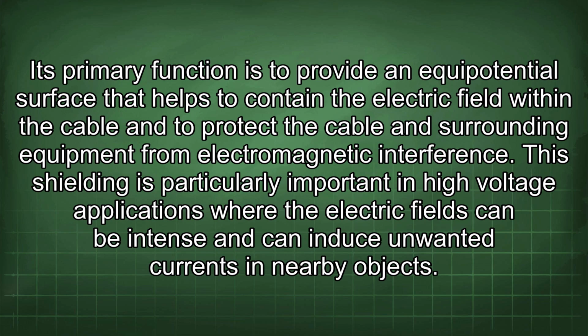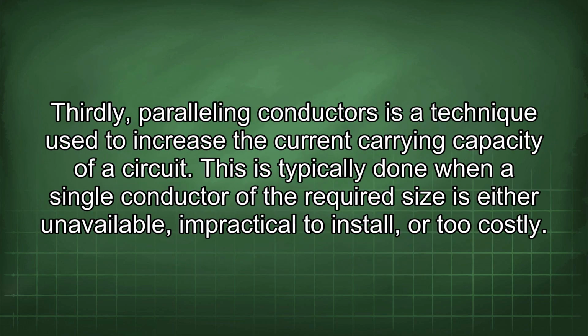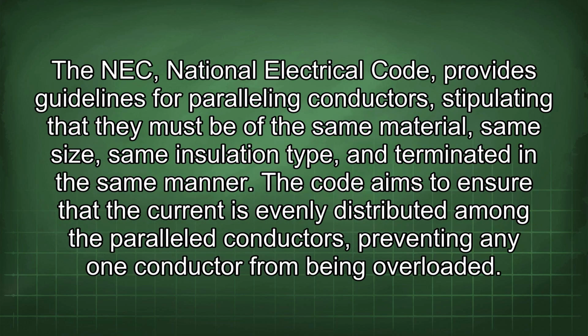The shielding is particularly important in high-voltage applications where the electric fields can be intense and can induce unwanted currents in nearby objects. Thirdly, paralleling conductors is a technique used to increase the current carrying capacity of a circuit. This is typically done when a single conductor of the required size is either unavailable, impractical to install, or too costly. The NEC, National Electrical Code, provides guidelines for paralleling conductors, stipulating that they must be of the same material, same size, same insulation type, and terminated in the same manner. The code aims to ensure that the current is evenly distributed among the parallel conductors, preventing any one conductor from being overloaded.